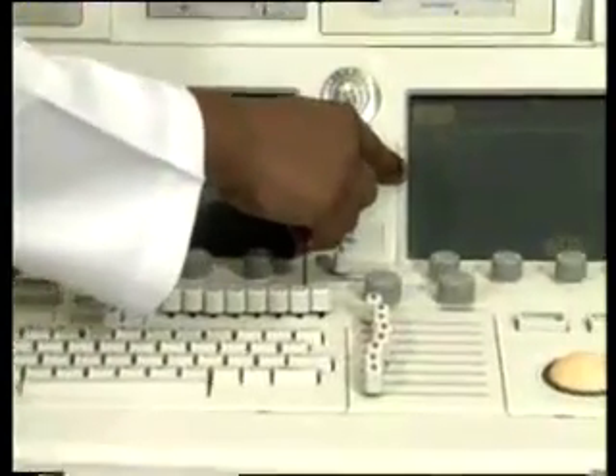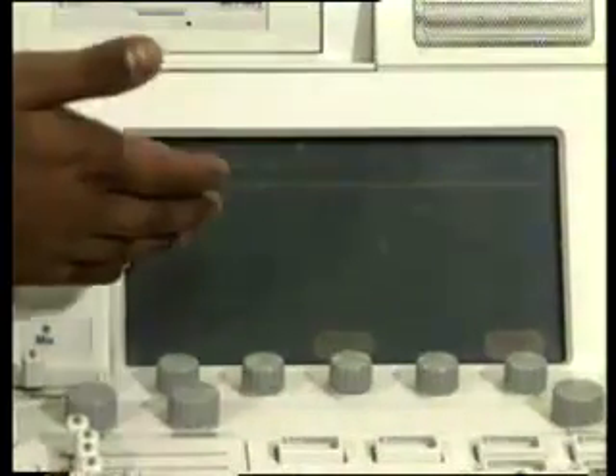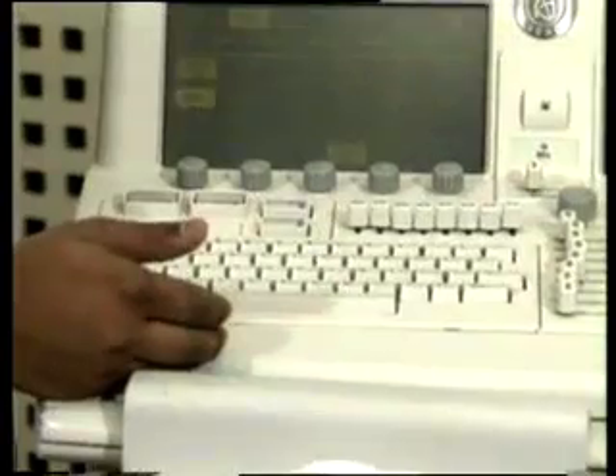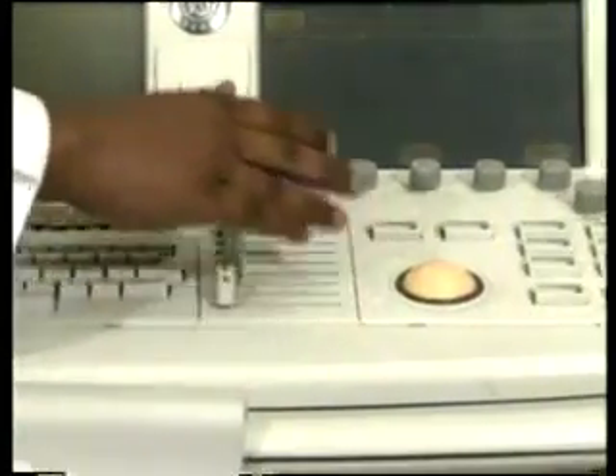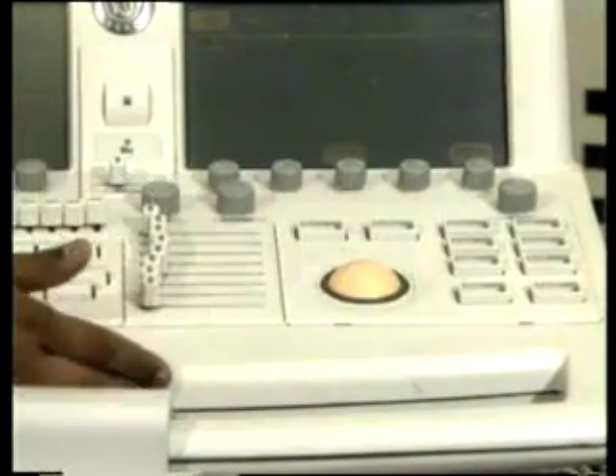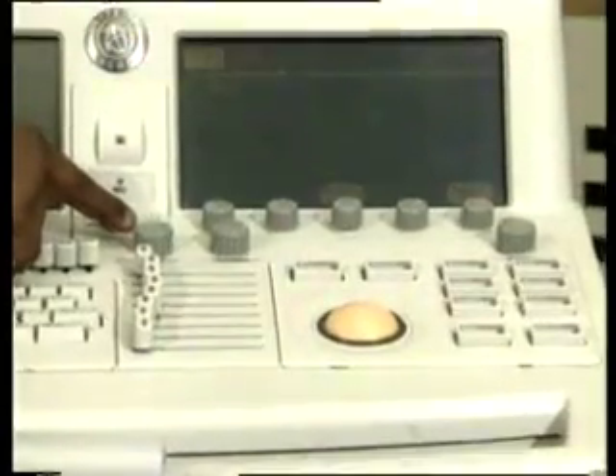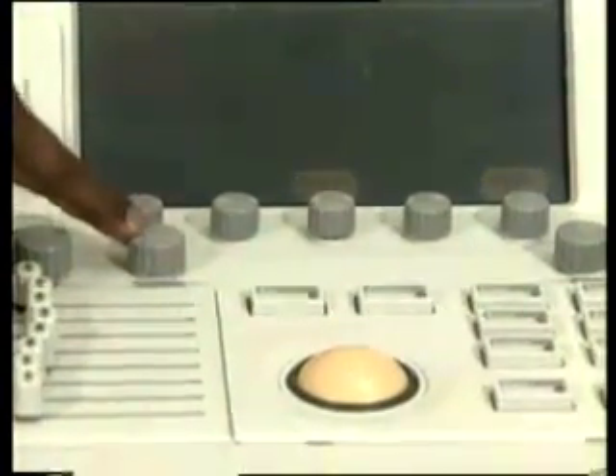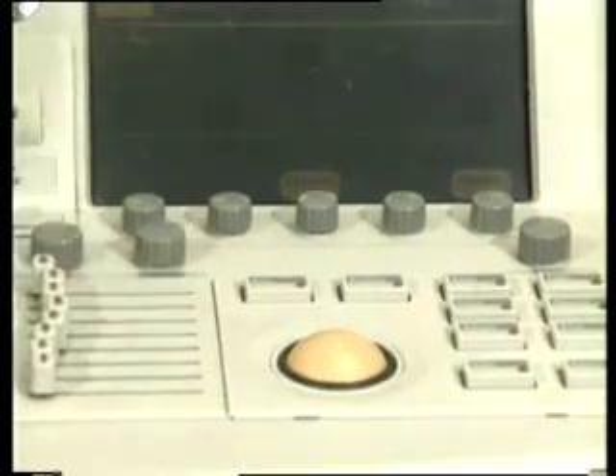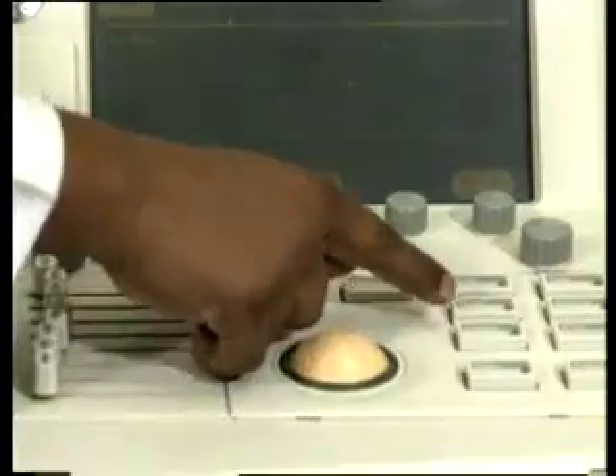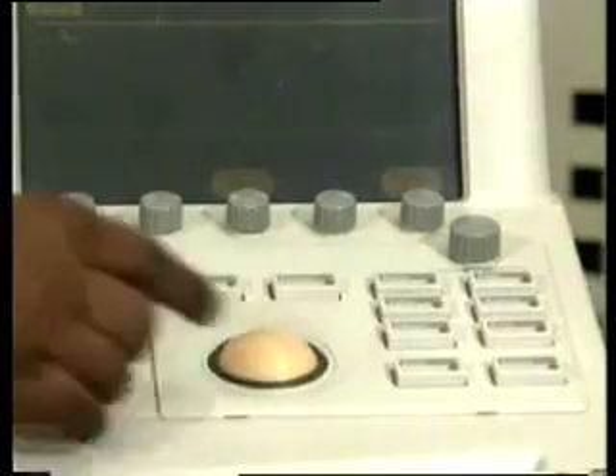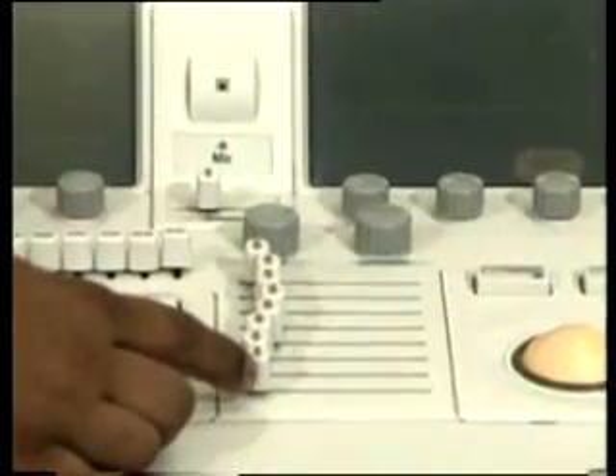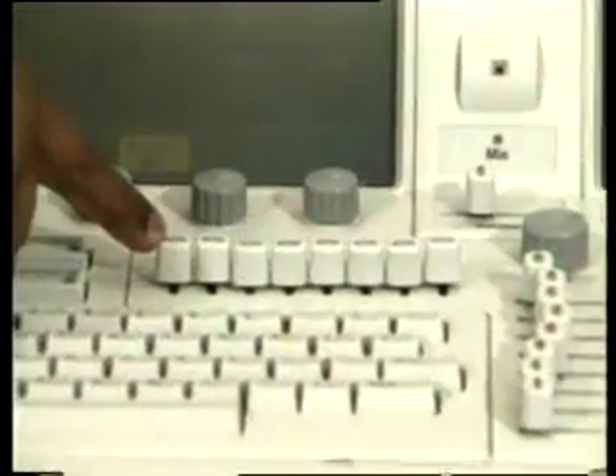This touch screen has controls which are specific for a particular examination, like whether we are going to use 2D or color Doppler or M mode. Likewise, this segment has a keyboard which is used for keying in text data, for example the patient's name and other information, and here are the controls which are used for adjusting the image and for deriving different types of information. This is the knob used for adjusting gain, this is for compress, this is for adjusting the size of the sector and the position of the sector. These are for measurements like caliper and trace. This is for adjusting time gain compensation or TGC. This is for lateral gain compensation or LGC.